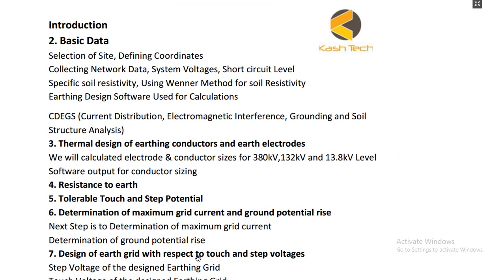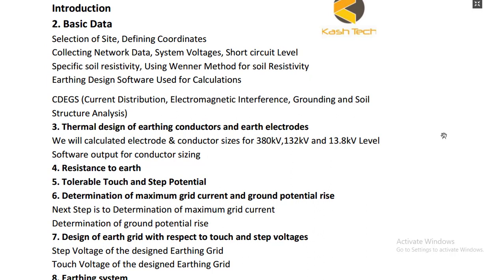We will start with an introduction and check the description of the site — basically the location where you want to build the substation. Then we will discuss network data. If you want to make a substation, you need the network data. The most important thing is how much the short circuit level will be, which obviously depends on how many sources are feeding and to which network it is connected, and also at which voltage level you are connecting the substation.